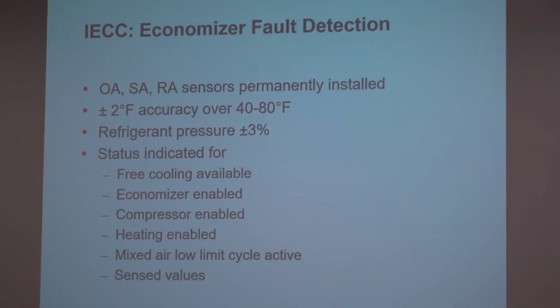So the economizer fault detection is on the next slide here. What we're talking about trying to figure out is when our sensors have gone bad or are broken or are reading improper numbers. So we want those sensors permanently installed. We don't want them only there for commissioning and then removed. So we're looking for some good accuracy over that range in the quality of the sensors that we're installing. So this is a design criteria for the sensor selection.